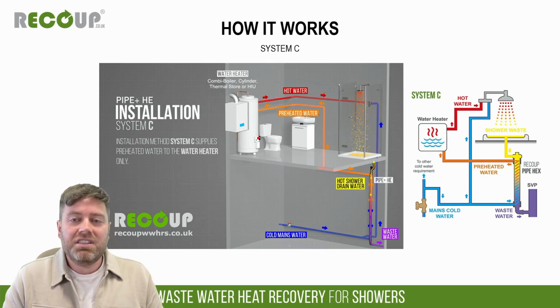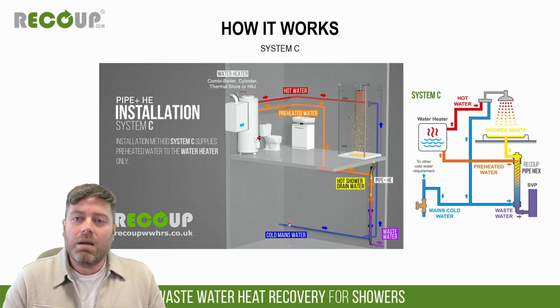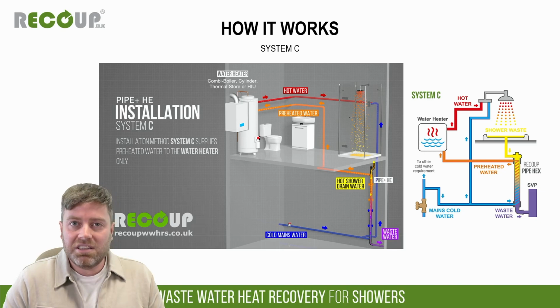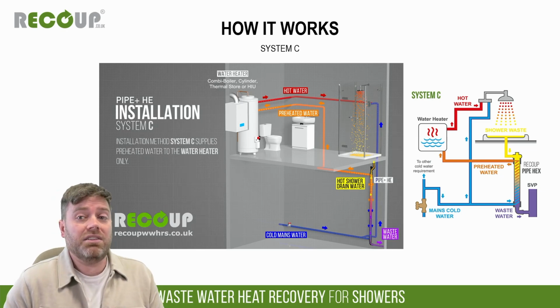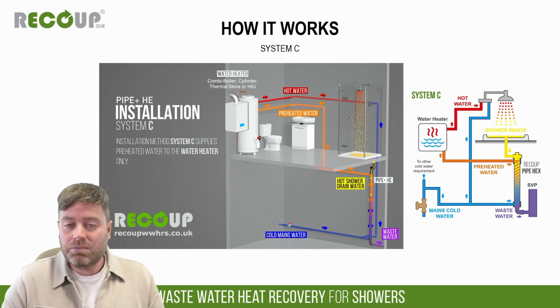In terms of efficiency, it sits between System A and B. We don't see it used that often for kind of non-residential applications. You get a few kind of specific niche situations where it might be considered, but it's the least common system to be used, and it's where you're just sending preheated water to your hot water source only, so you're not sending it to the shower. As I say, it wouldn't be specified that often, occasionally in specific circumstances, but you're normally looking at System A or B in most cases.